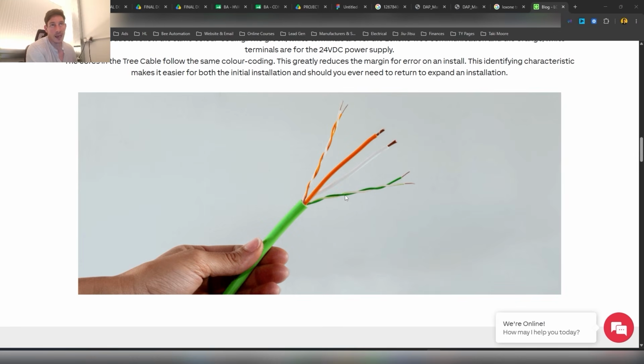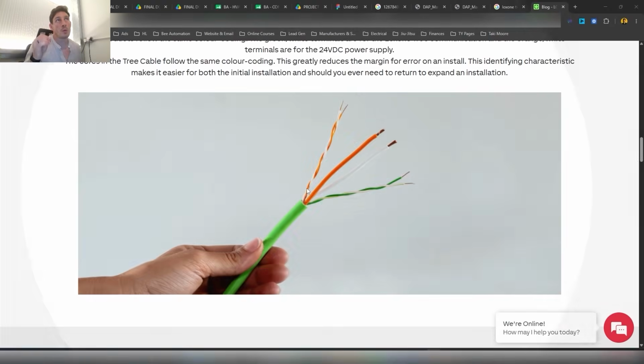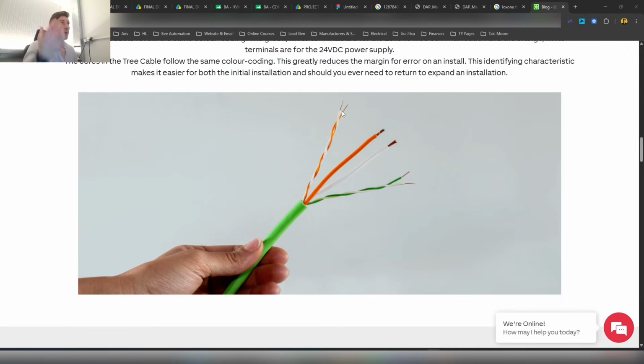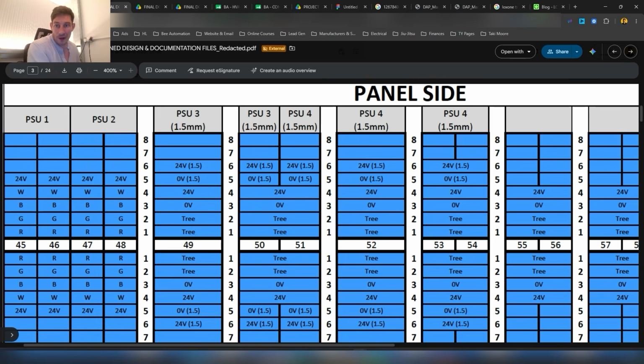It provides your tree comms, which we should already be familiar with. We're keeping the cable consistent outside the panel and inside the panel. So twisted green and white is the tree comms, and then we've got the twisted orange and white, which is the low power, low current peripheral power. Peripherals are things like the motion sensors, the touch switches, things that don't consume much power. And then we've got the thicker 1.5 mil cables for things that require more power, like the lights, the RGBW spots. So hopefully that'll give you a bit of context.